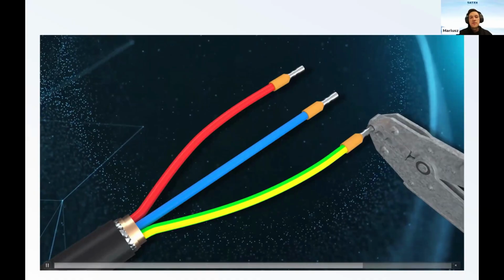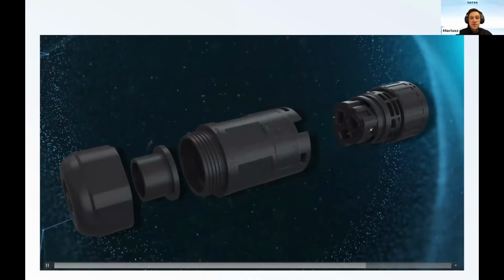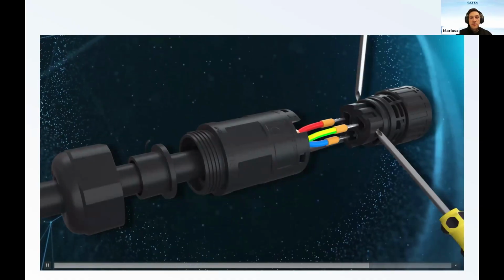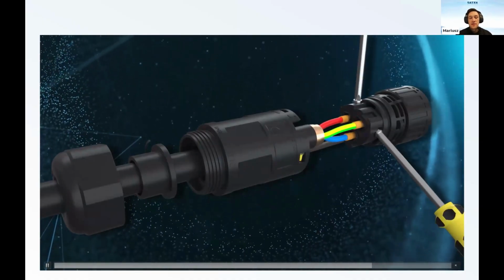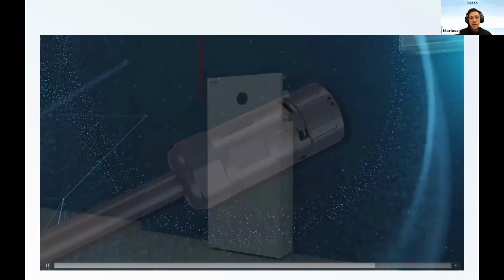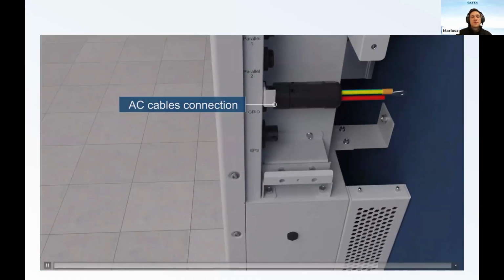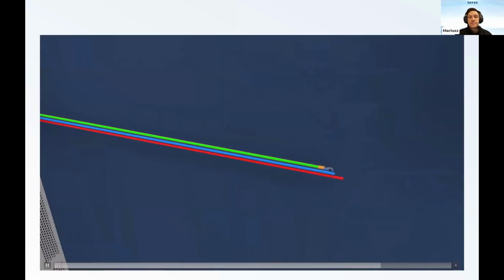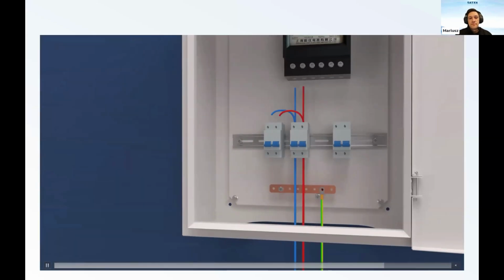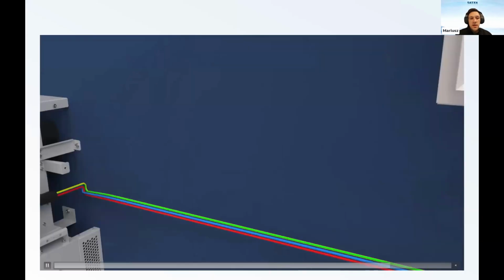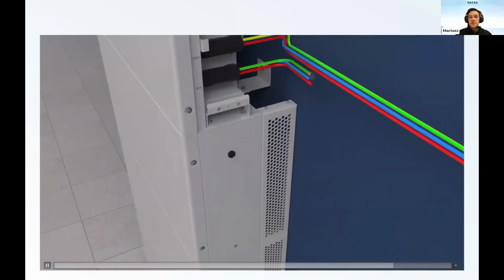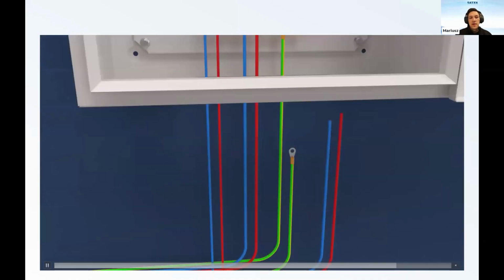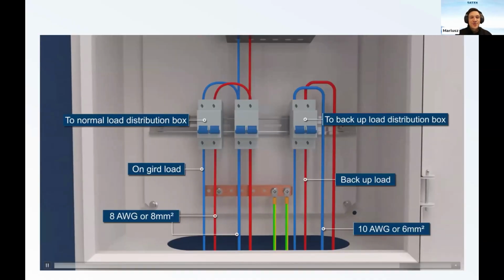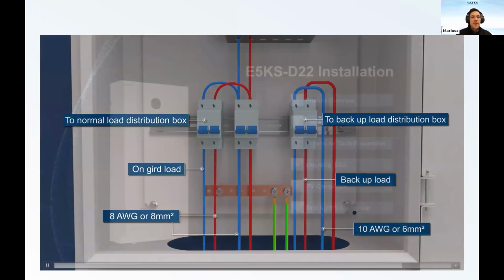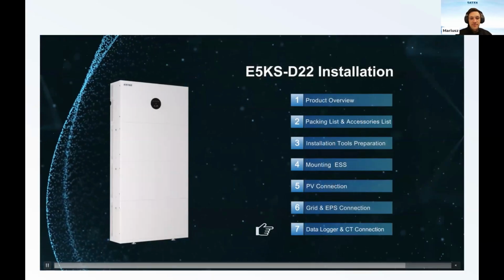And also, if we are connecting the parallel solution, it's very important to keep the same outputs. I mean, all of the backup outputs to the backup power line, and all of the grid outputs to the grid power line. And also be aware that before each inverter, in case of any maintenance service, there should be an AC circuit breaker installed. I think it's quite a standard solution, but it's better to mention it.